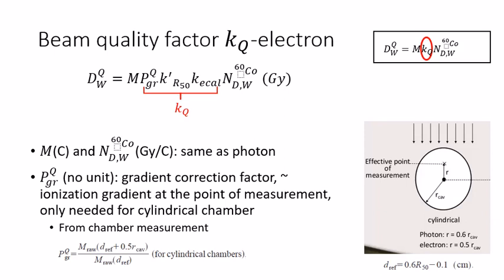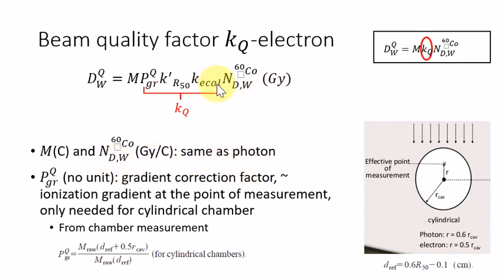Let's take a look at how to obtain the beam quality factor for electron beam. For electron beam compared to photon beam, it's slightly complicated. The KQ factor actually equals three factors multiplied together, if you look at this TG51 formula. In this formula, the corrected chamber reading and the NDW Co-60 factors are the same as photons. What's left is the KQ factor.